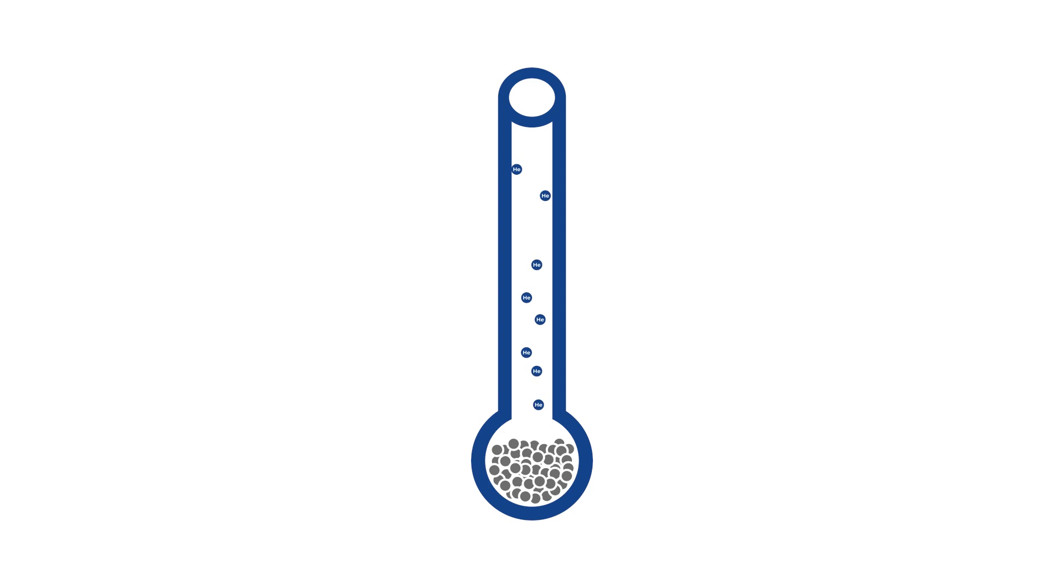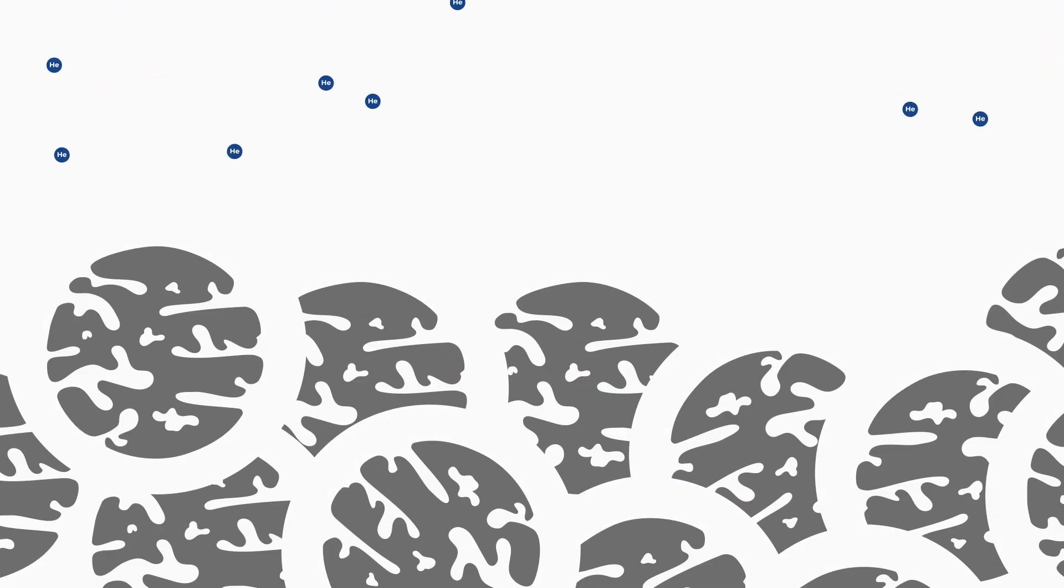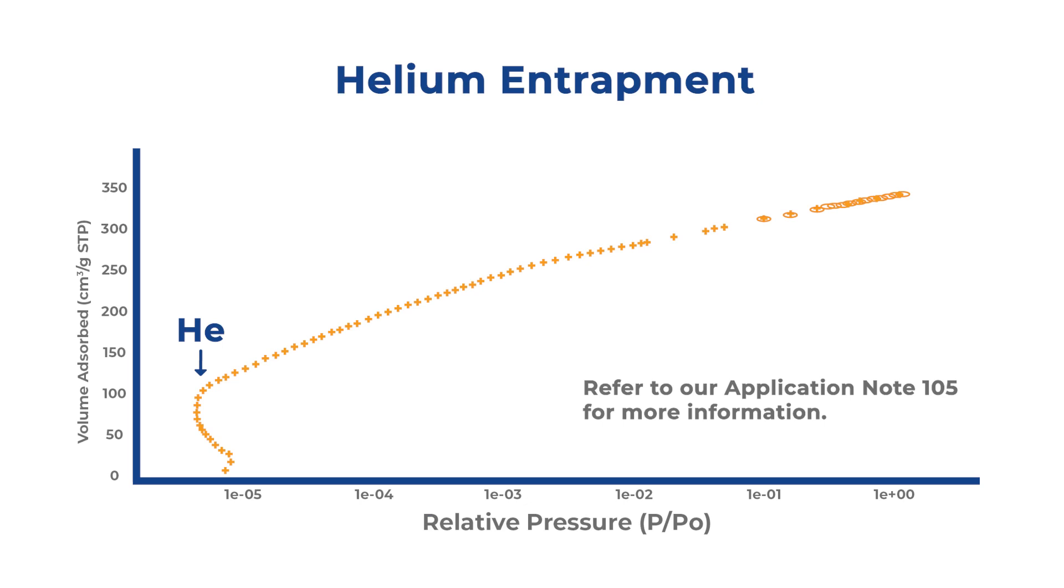However, there are some exceptions. For microporous samples, helium is known to get trapped in their small pores so that the result often gets compromised from helium desorption at low pressures when the free space is measured before analysis.